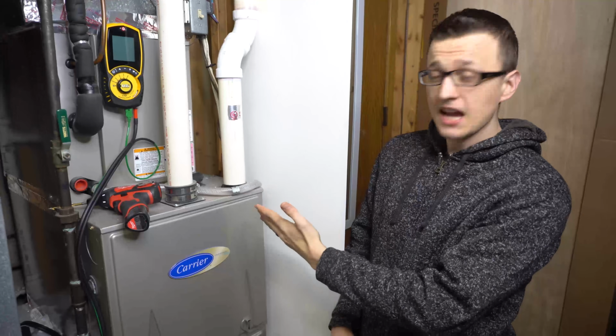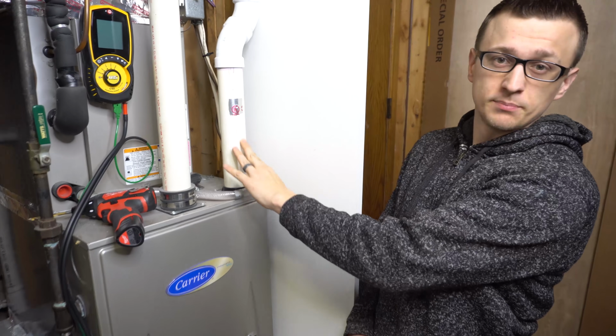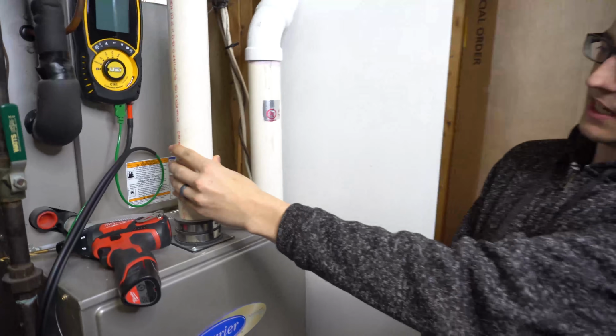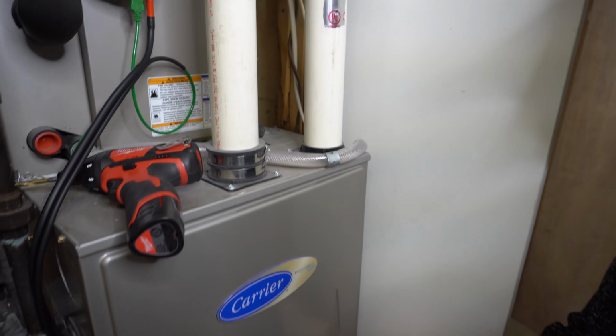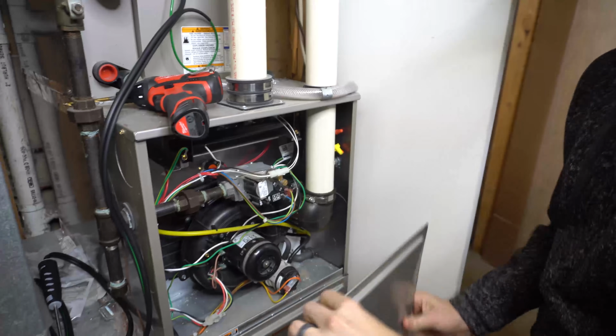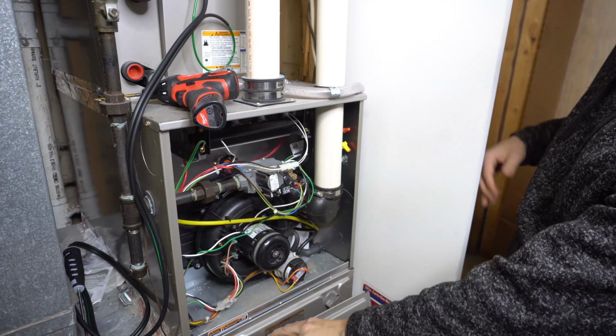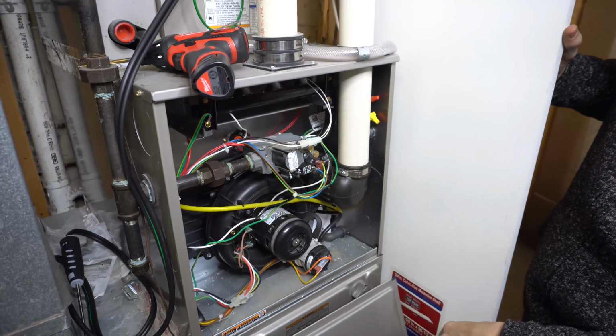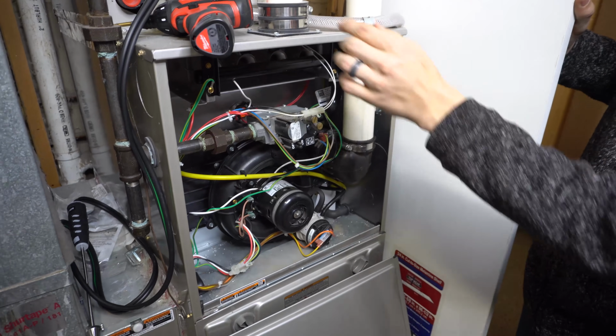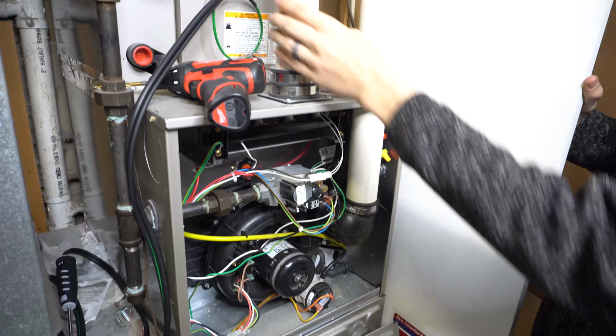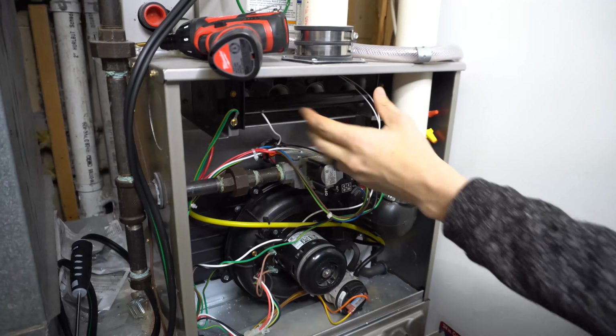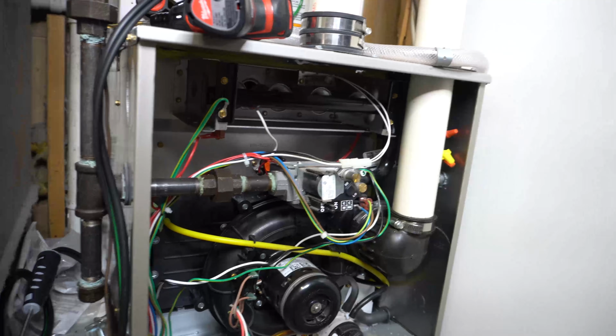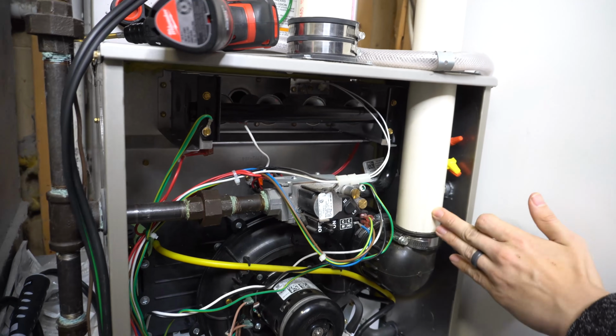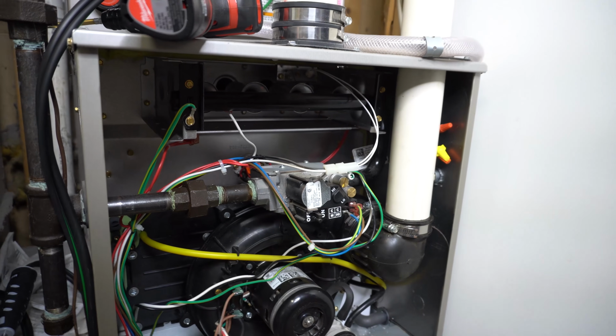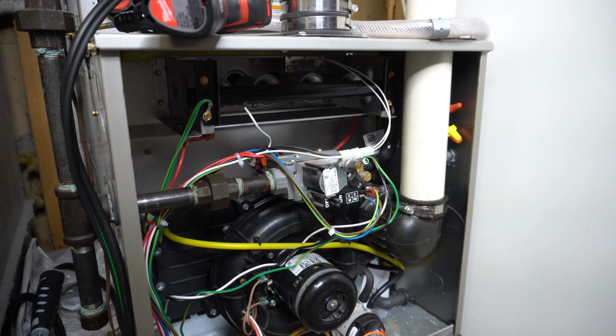Okay, so now we're at a high efficiency furnace, which has plastic PVC venting. It also has an intake pipe. And if you're not sure which pipe is the intake and which is the exhaust, if you just take the top door off, that's going to be pretty easy to tell. Basically, the intake pipe is always going to be going to your burner box to provide the oxygen for the flames, whereas the exhaust pipe is always going to be going to your inducer motor, exhausting the combustion fumes.